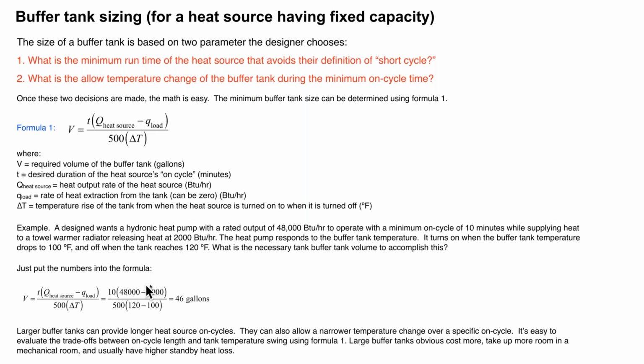So really, it's just a matter of putting those numbers into this formula, all right? And it calculates out to be 46 gallons, okay? Now, again, that's a theoretical estimate for the volume. You know, if you put a 50-gallon tank in, that'd be fine. If you put a 40-gallon tank in, the run time is going to go down a little bit.